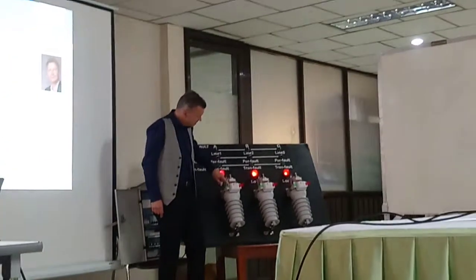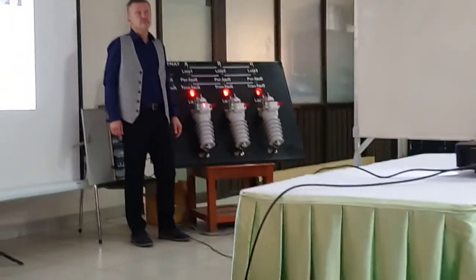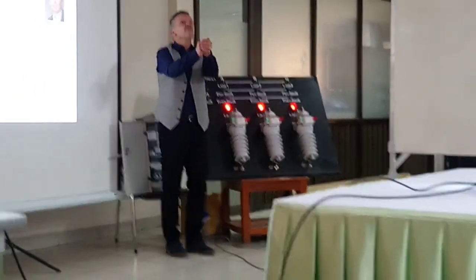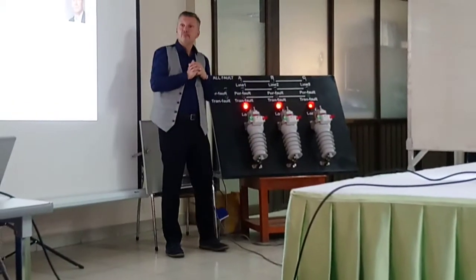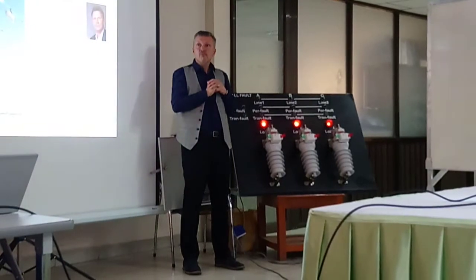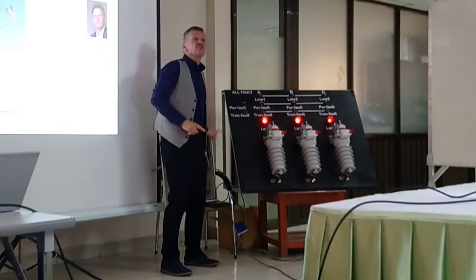And how to operate Fuse Saver by hand? Just press that button here. You need a long stick. Press it with a hook stick, the same one you use to replace the fuse, to pull the fuse down. There's a small trick.